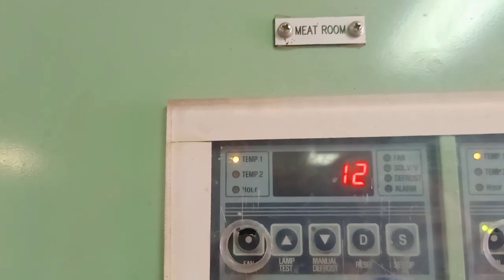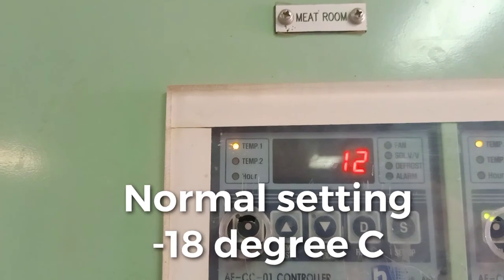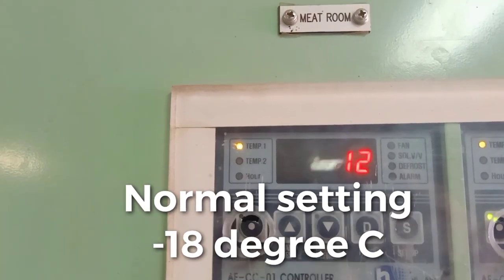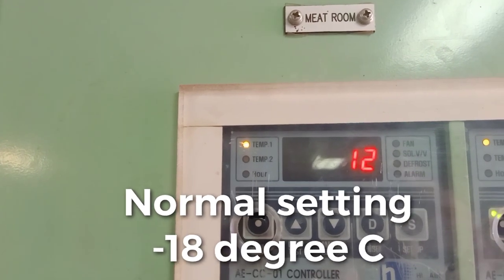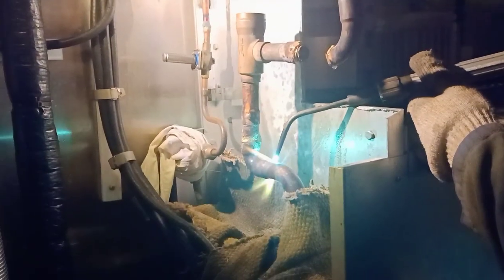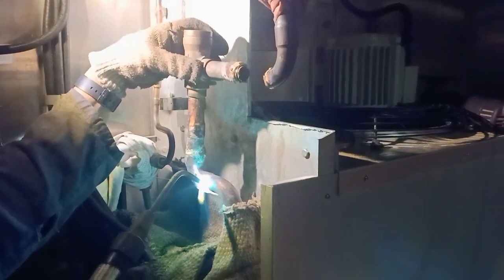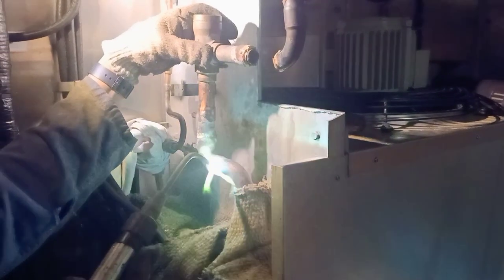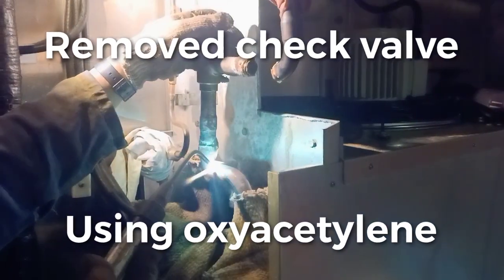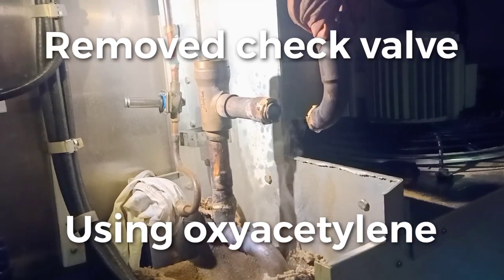This is the reading of our meat chamber. Normally the set temperature is negative 18°C. We are about to remove the non-return valve using our oxy-acetylene. Normally the pressure will flow here — one bar, one point five bar, two bars.